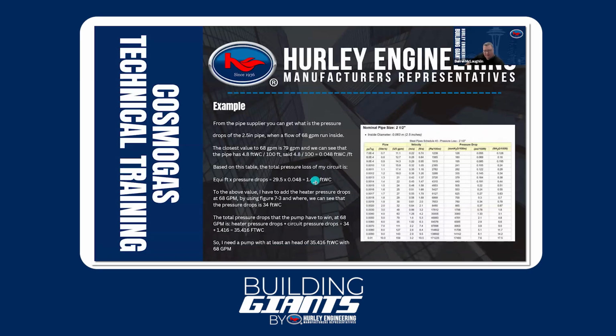Now, in reality, it's only about a 5% difference, and that's pretty consistent across the board. So you can just account for that at 5%, and as long as you're not within that range, move forward. But if you start getting close, then you need to rethink, run the calculations, and make sure that you're sizing the pump correctly. Because again, low flow in that F1 zone is going to be your enemy in this boiler.